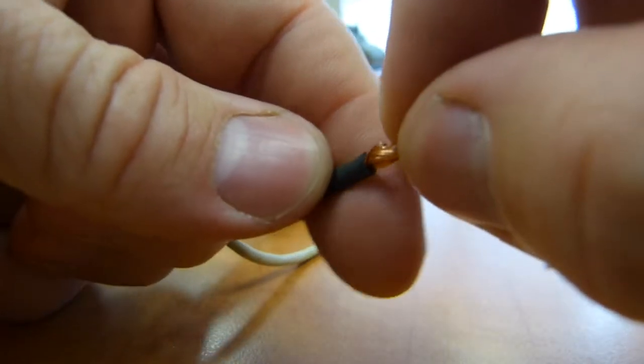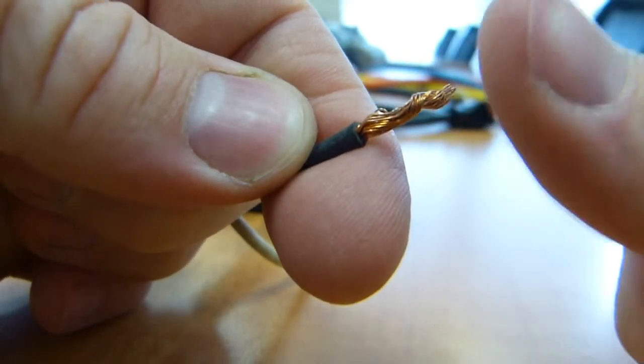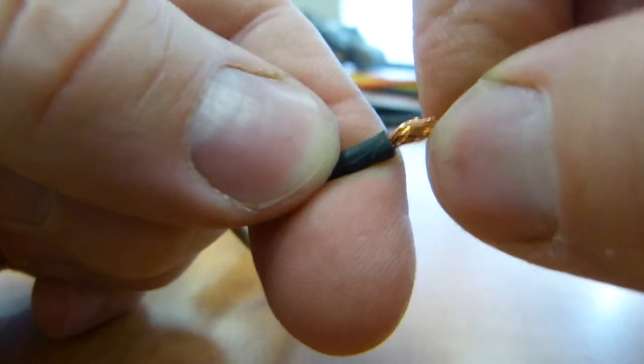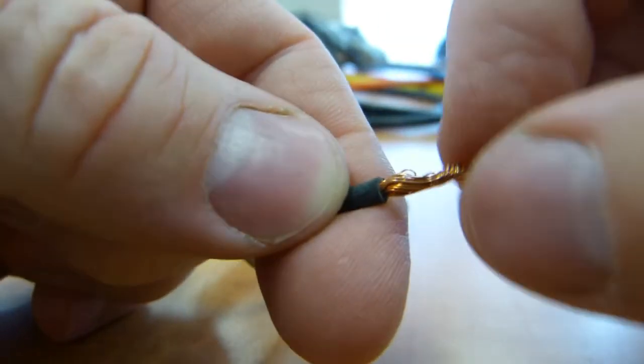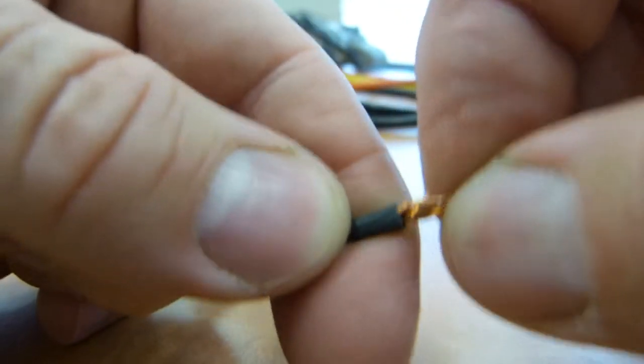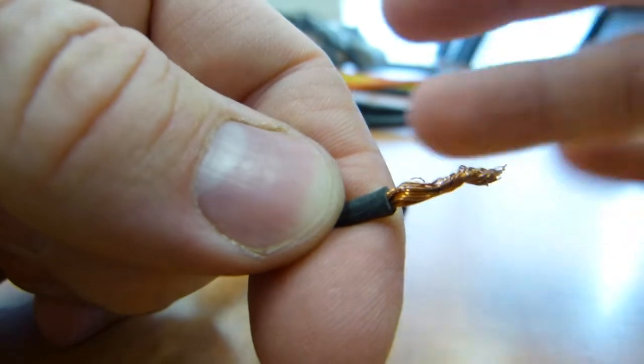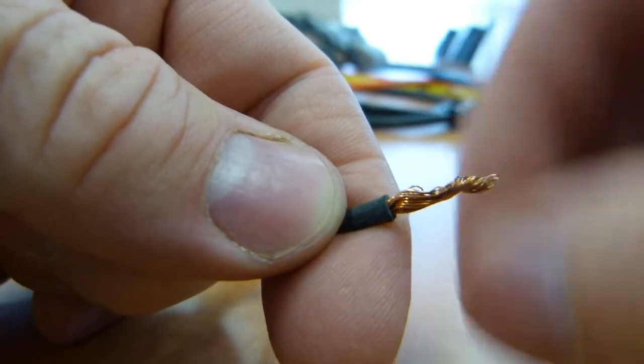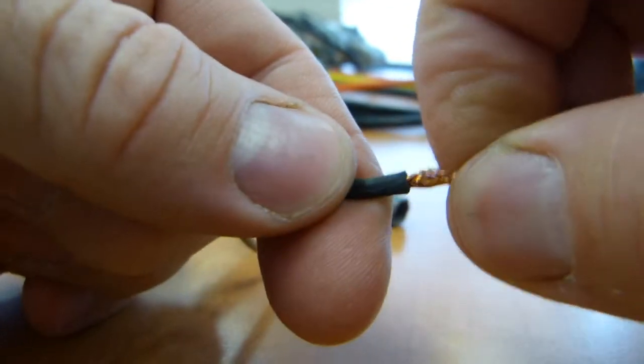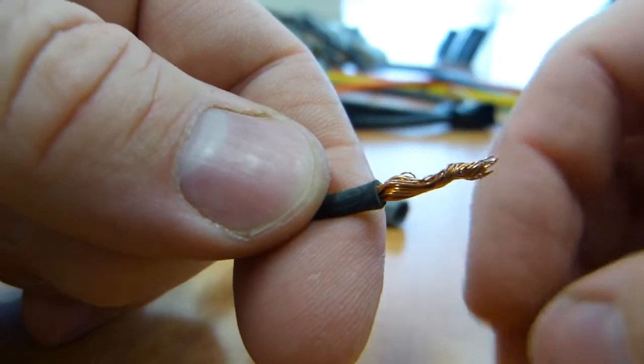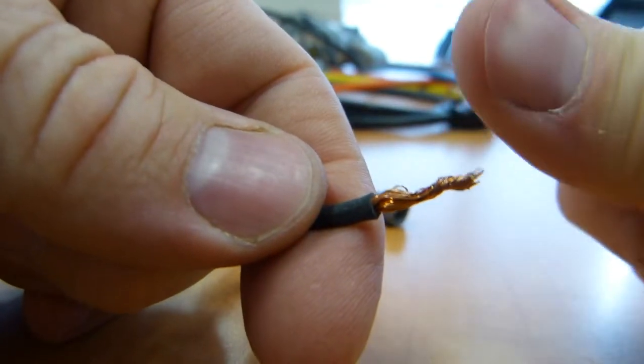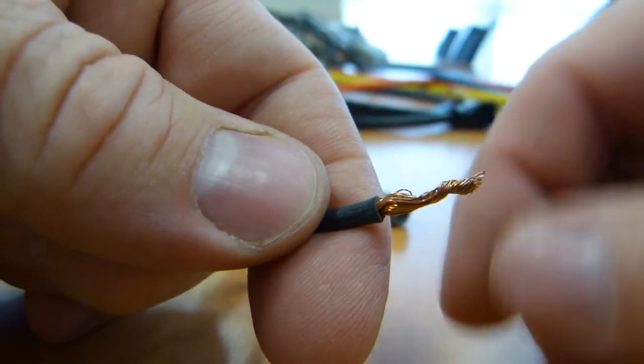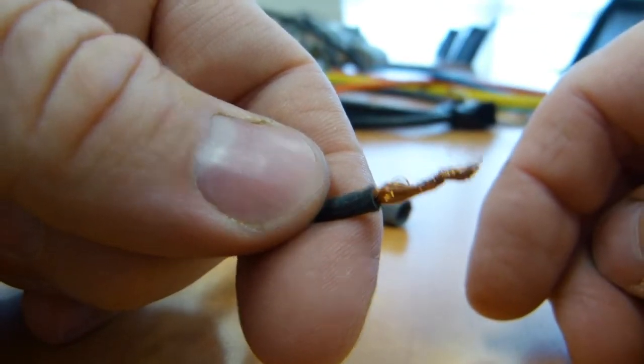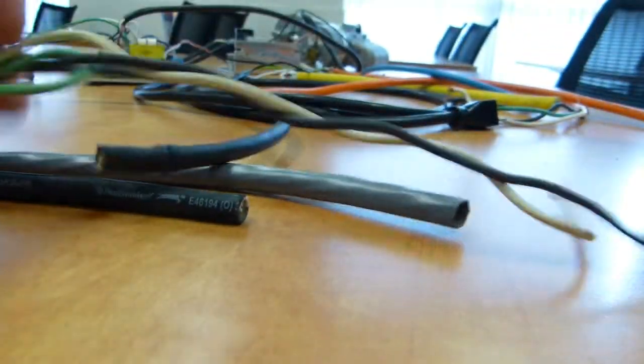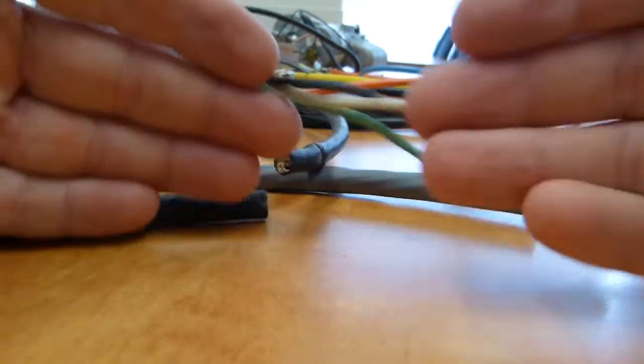The ampacity or amp carrying or electrical load carrying capability of this conductor decreases when the temperature rises. So this might be rated for 15 amps, and I'm just inventing these numbers a little bit, but we'll pretend it's a round number, say 15 amps for this one at room temperature, 30 degrees, something like that. If the temperature goes up to 50 degrees, instead of 15 amps, it can only do 14.5. And the temperature keeps rising, 14. Temperature keeps rising to 100 degrees, I don't know, 12.5, something like that, sometimes a lot less.